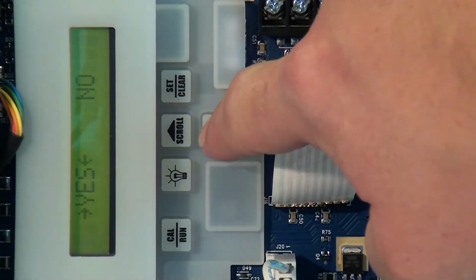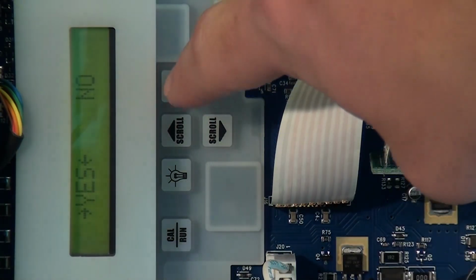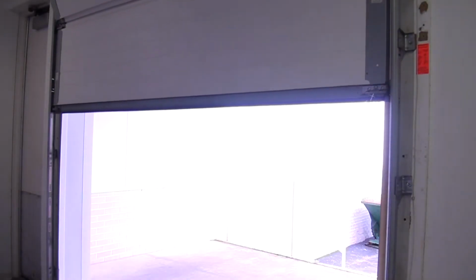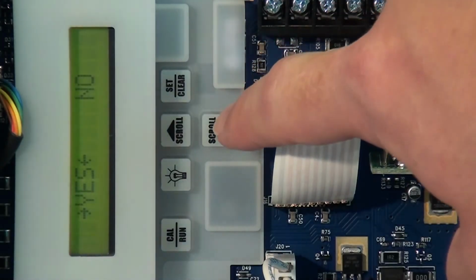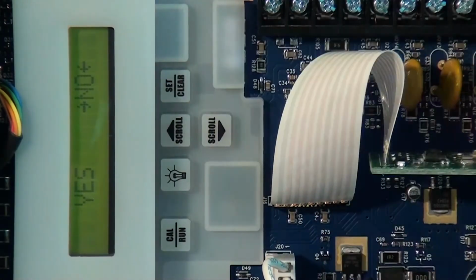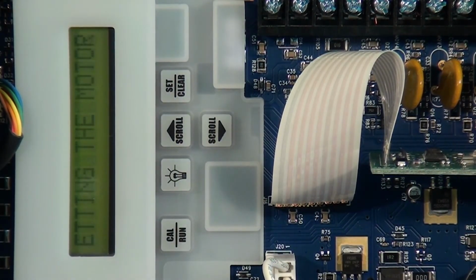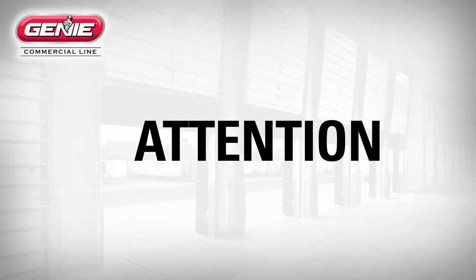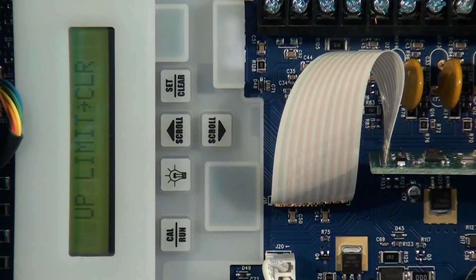If the door moved in a closed direction, scroll to Yes, and then press the Set Clear key. If the door moved in the open direction, scroll to No, and then press the Set Clear key. The display will read, Now setting the motor direction. The display will automatically advance to Up Limit Clear once the motor direction is set. Anytime the motor direction is reset, the open and close limits will automatically clear and need reset. Press the calibration run key to return to run mode.